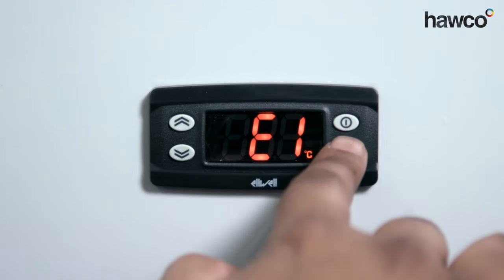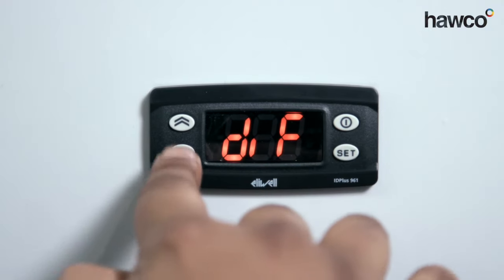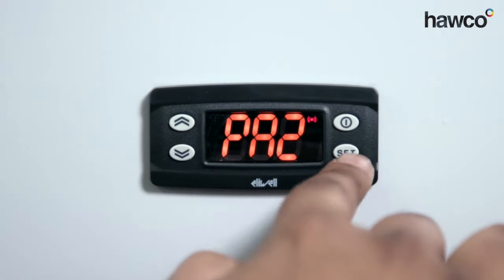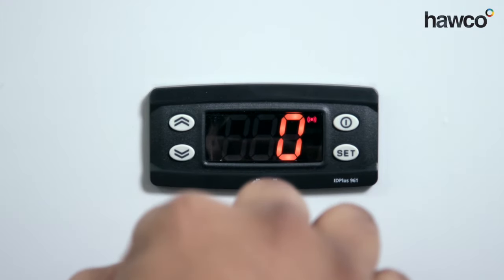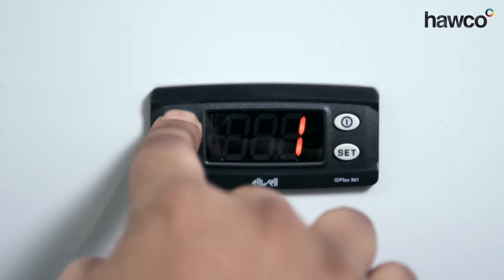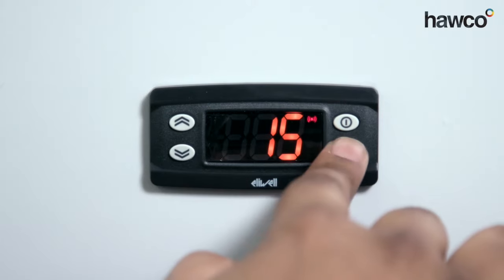So we're going to enter the installer parameters by pressing and holding the set button for a few seconds. We're going to go through to PA2, which is password 2. We're going to press set on there. Eliwell's default password is always 15, so we're going to take this up to 15 and press set.